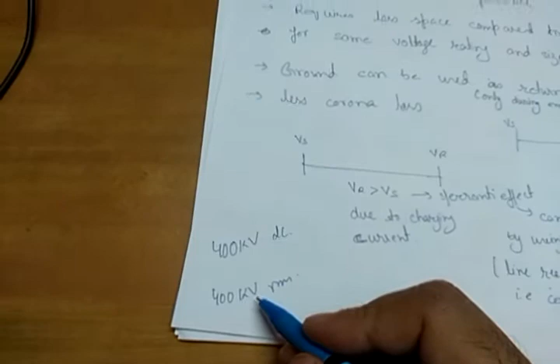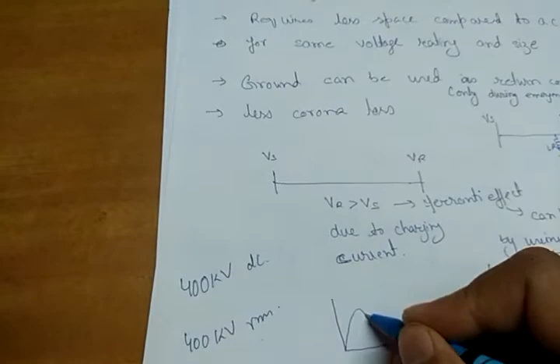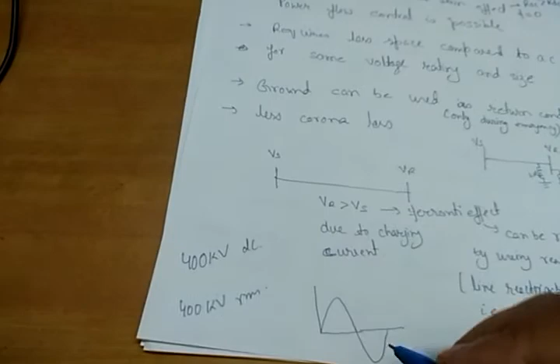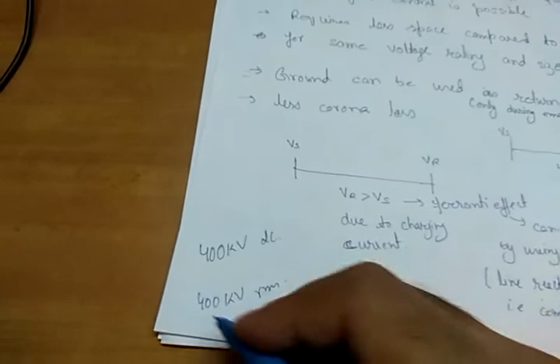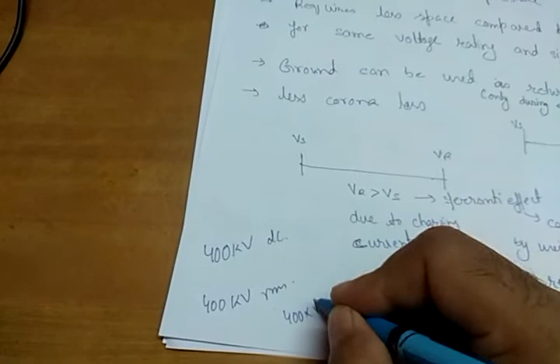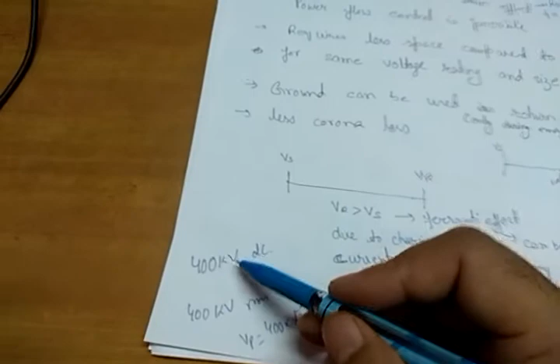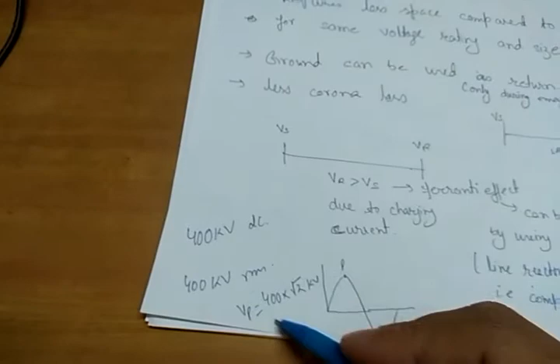But we have to design the system differently. Whenever we design AC, we design it for the peak value. If 400 kilovolt is the RMS, the peak will be 400 multiplied by root 2 kilovolt. So if we are designing for a 400 kV DC, in the case of AC we will have to design for 400 multiplied by root 2 kilovolt, the peak value. Obviously this value will be more.